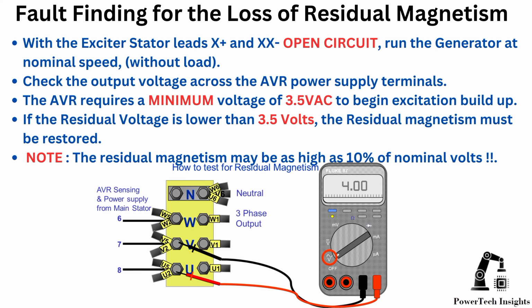With the exciter stator leads X plus and XX negative open circuit, run the generator at nominal speed without load. Check the output voltage across the AVR power supply terminals. The AVR requires a minimum voltage of 3.5 VAC to begin excitation build-up. If the residual voltage is lower than 3.5 volts, the residual magnetism must be restored.